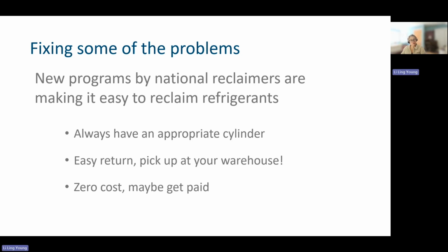The program that I'm most familiar with is Hudson Technologies program. To get involved there, you just set up an account online. When you have refrigerant that is ready to go back to the reclaimer, you order a pickup online. They'll send a truck out to your facility. If the quality of the refrigerant is high enough when they test it, they will pay you for the market value of that refrigerant, and they'll send you a replacement cylinder for the cylinder you sent to them.